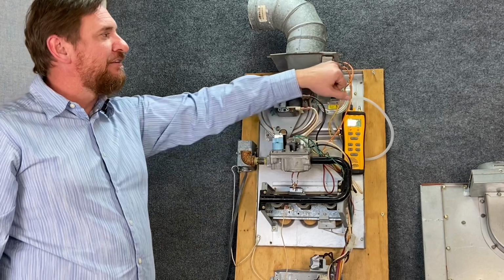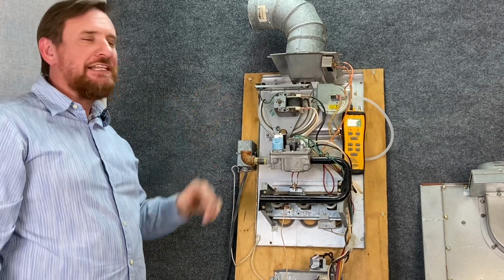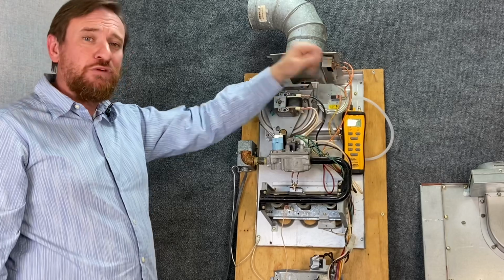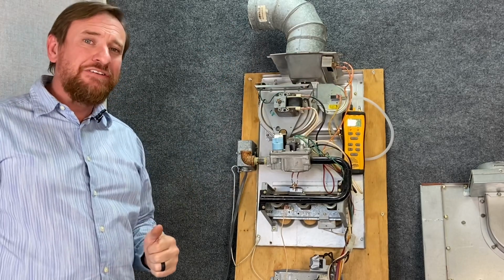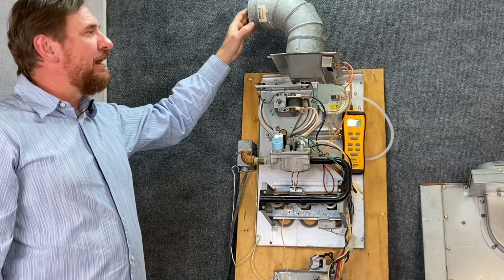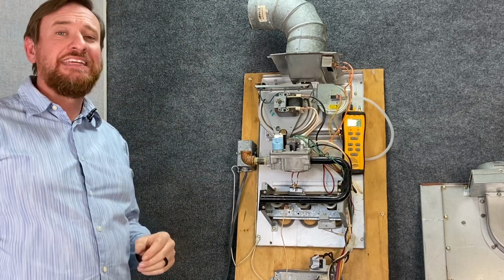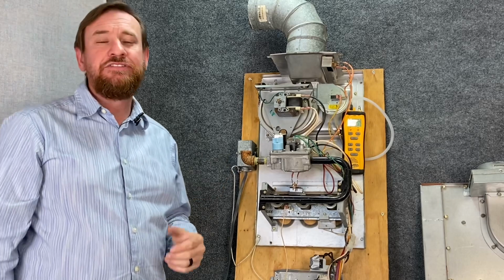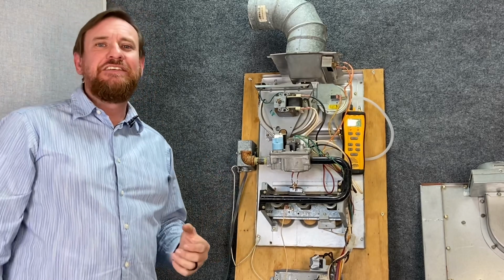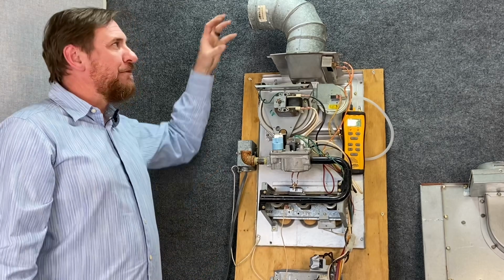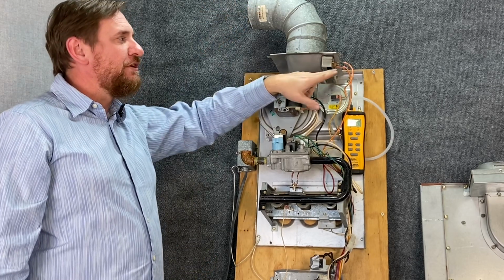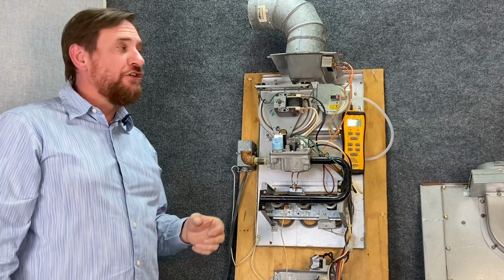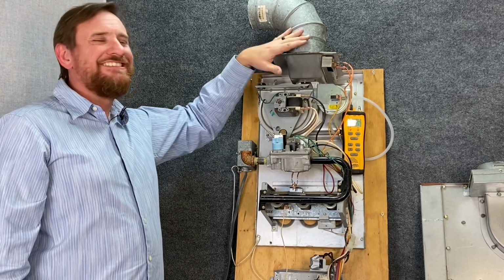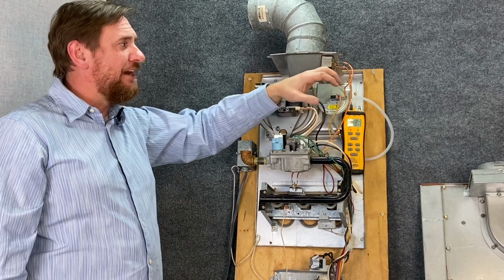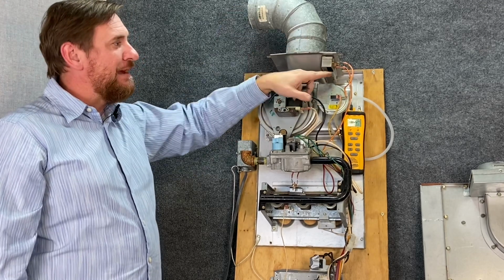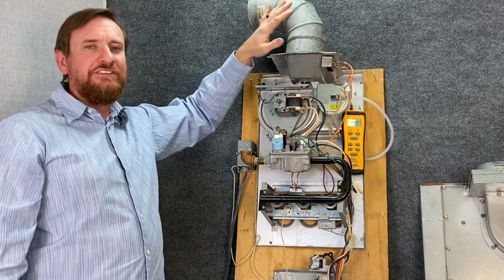And just like a rollout, this is manual reset, which means it's not going to automatically retry. It says, hey, if this tripped, we have a big problem. Somebody needs to come out and inspect our furnace. We need to inspect the flue pipe, the top, and the cap. I've seen it where it's had bird nests or bee nests inside of it, or hailstorms completely crushed the cap, and we can't get the flue gas out. So these switches are very important. Not every manufacturer uses them, but it also goes to show you that this is negative pressure, natural draft. It's actually pulling air in through here. If air starts coming back out of that, you know you have an issue with your exhaust or your flue.